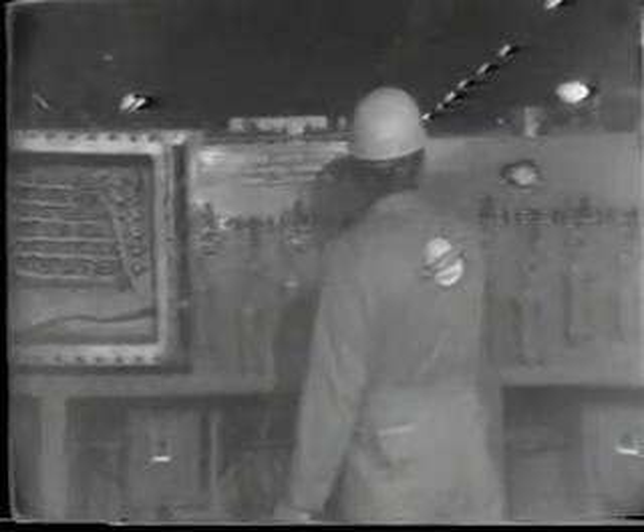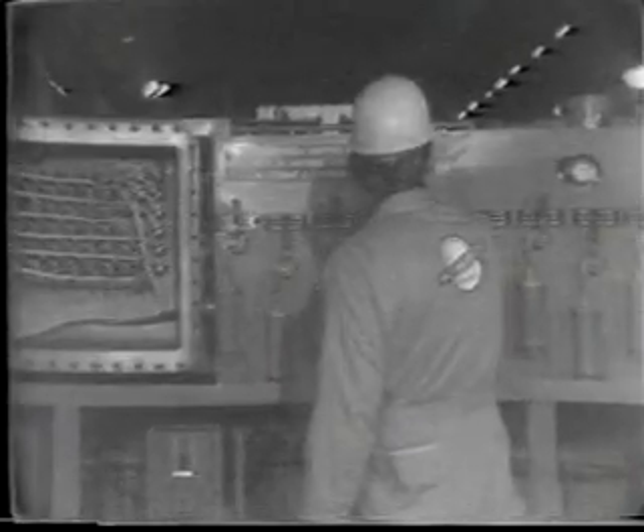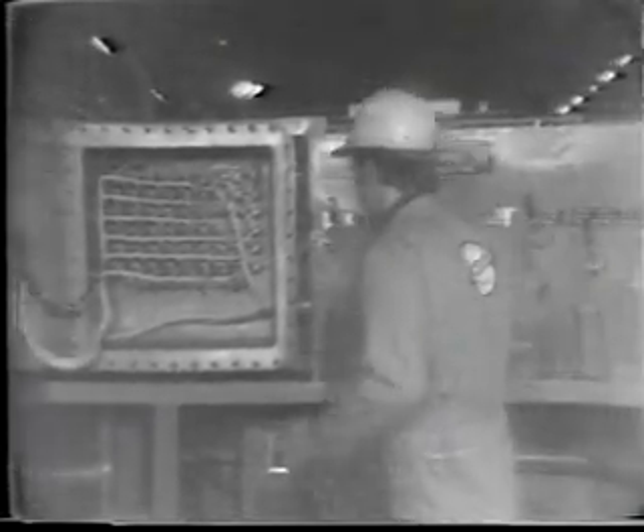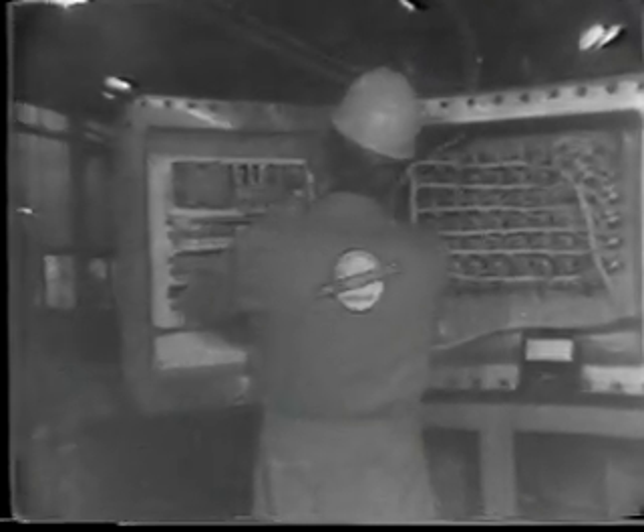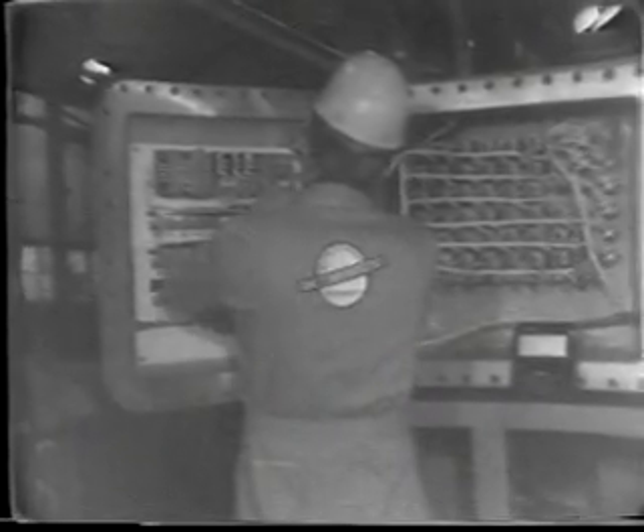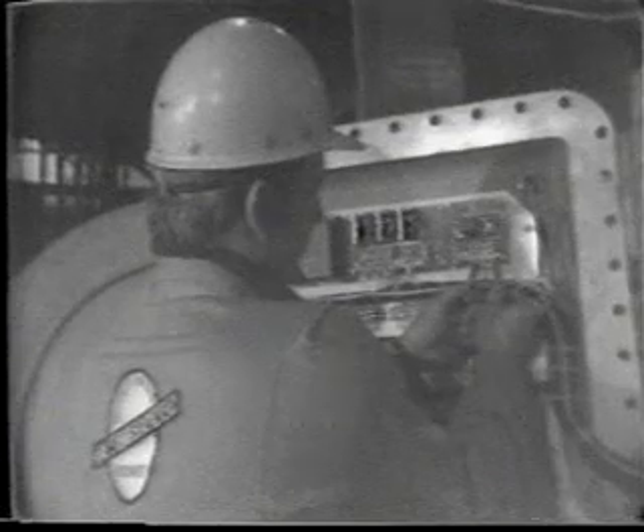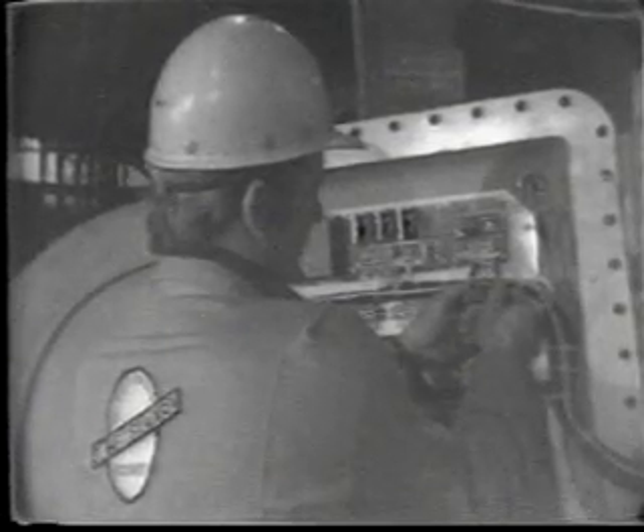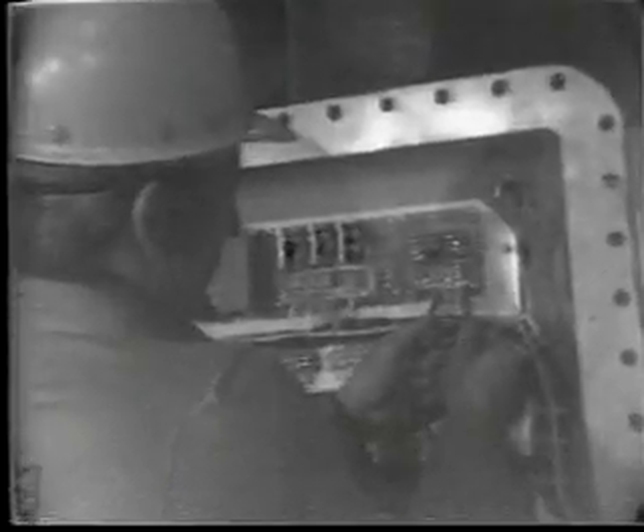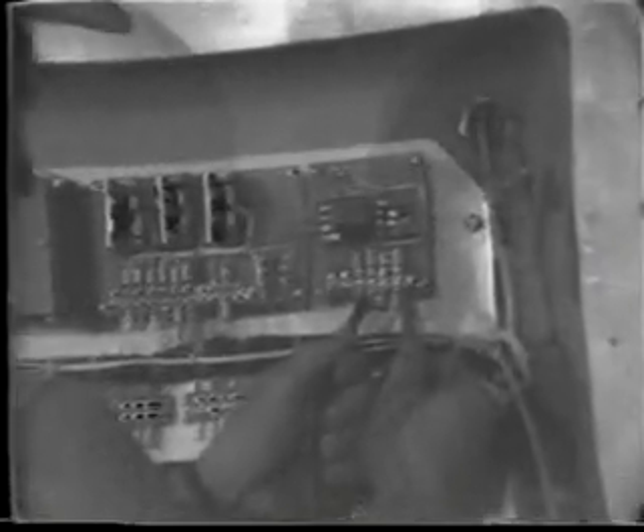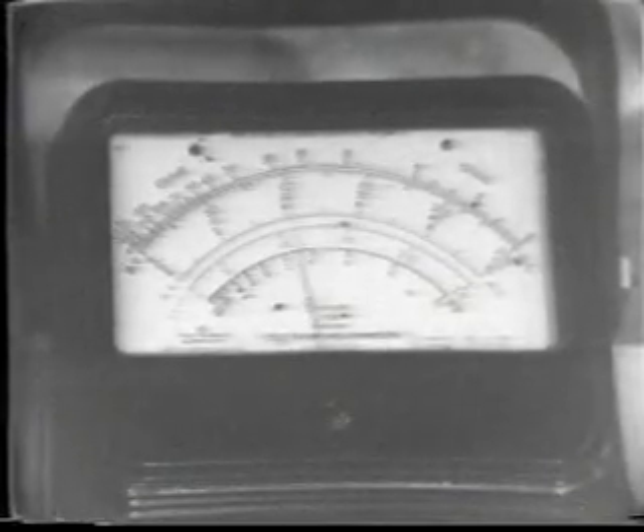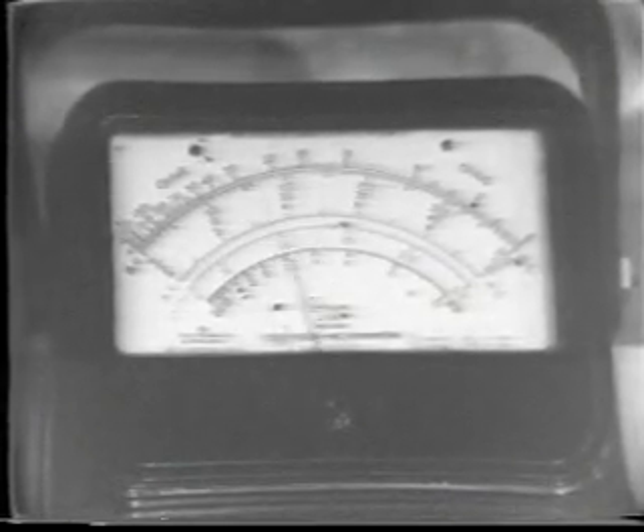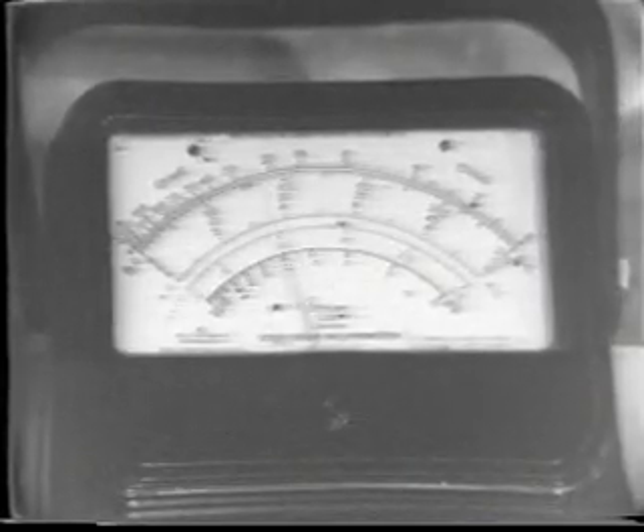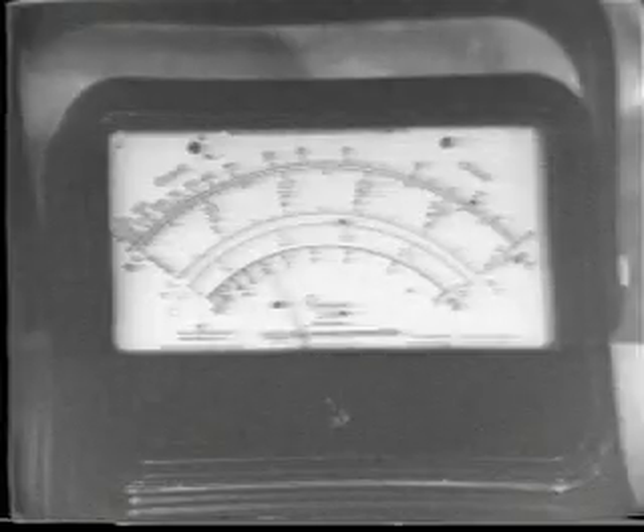Next, we will consider flow meter malfunction at the remote panels. If a function is activated and a fluid flow is indicated on the manifold flow meter but not on the remote panels, the first thing to check is the input power to the count circuit relay coil in the panel. Refer to the schematic for the proper terminals and check the voltage while fluid is flowing through the system. You should read a pulsating voltage. If you read a pulsating voltage, then check the continuity to the panel meter and the meter itself to see where the problem is.